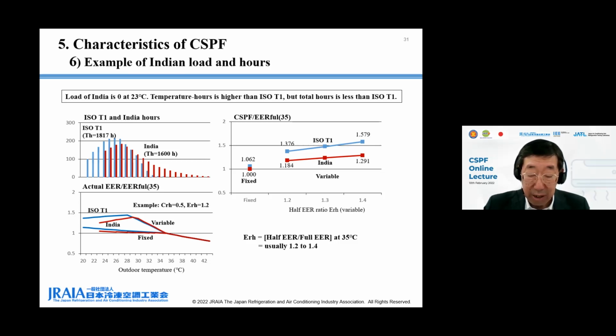On the other hand, actual EER over 35 degrees C is equal to full EER, and same for fixed capacity and variable capacity units. The right figure shows CSPF divided by 35 degrees C full EER of ISO T1 and India for fixed capacity unit and variable capacity unit in usual range of half EER ratio from 1.2 to 1.4. CSPF of variable capacity unit for India is 20 to 30% higher than for fixed capacity unit. This is significantly lower than the case of ISO T1 climate.